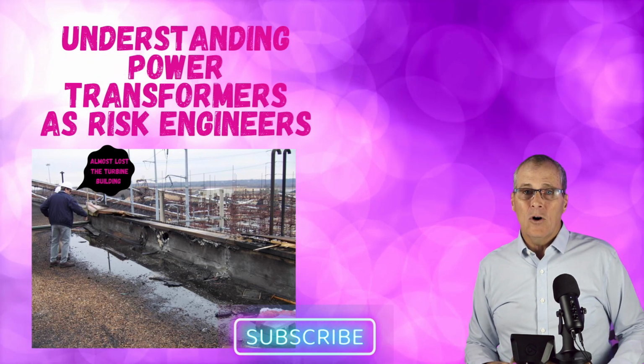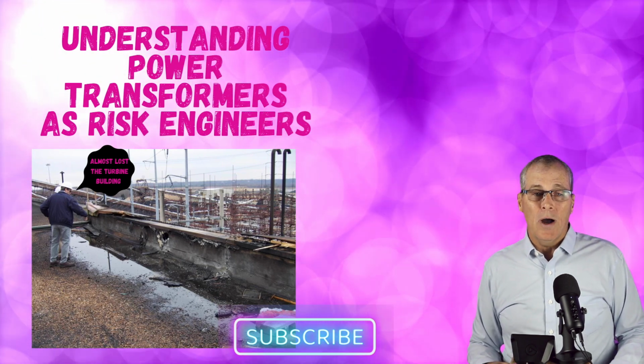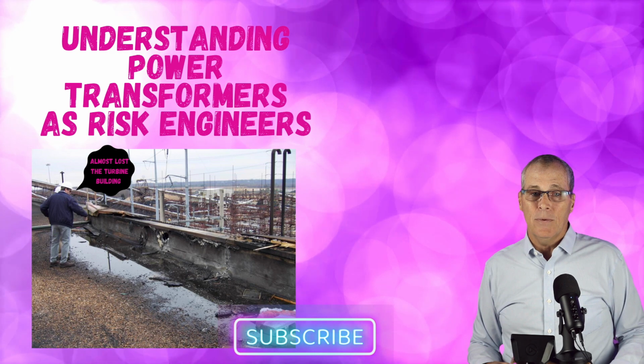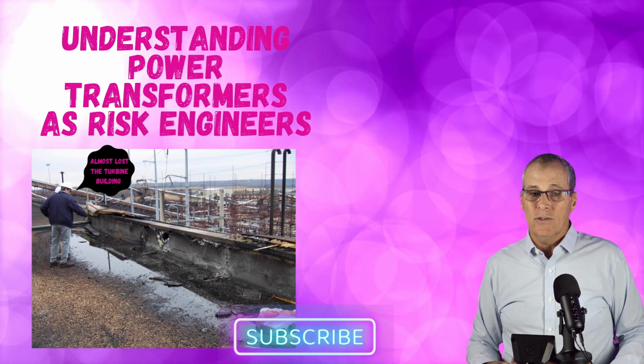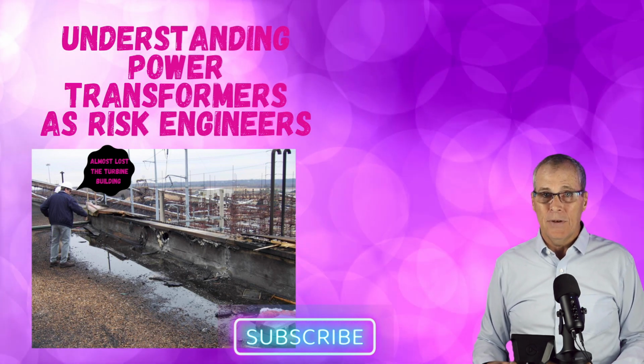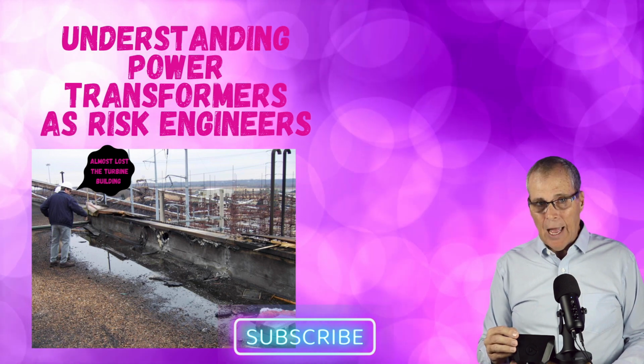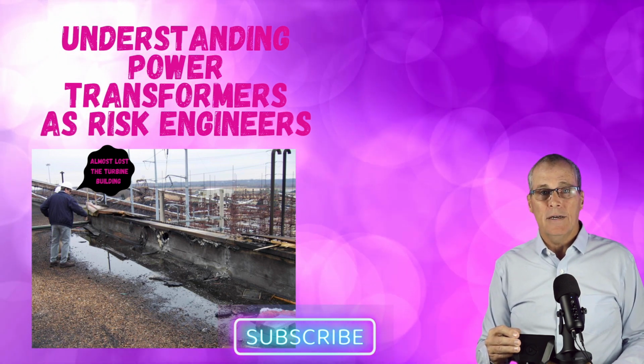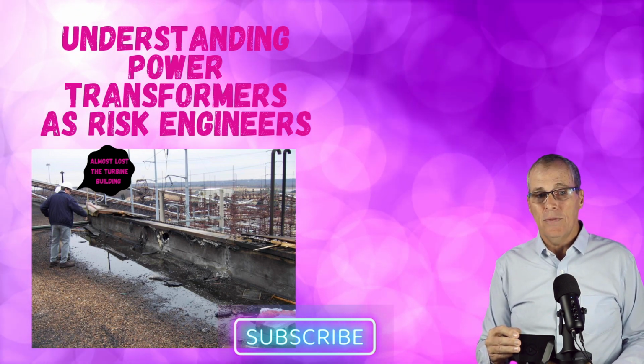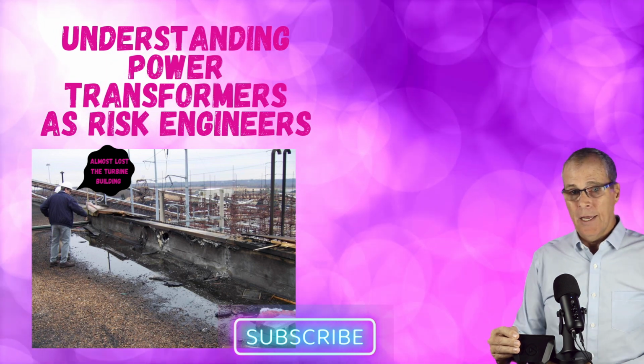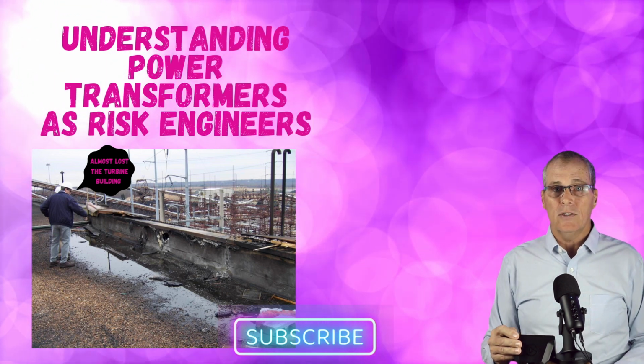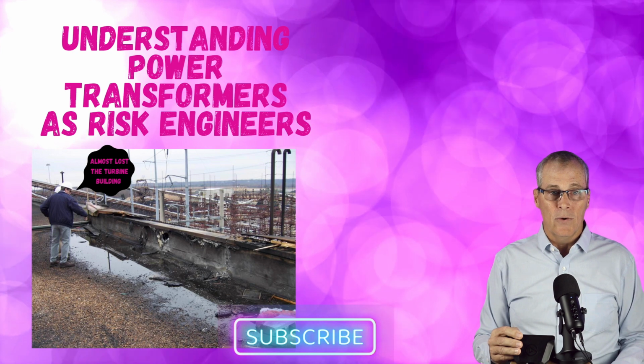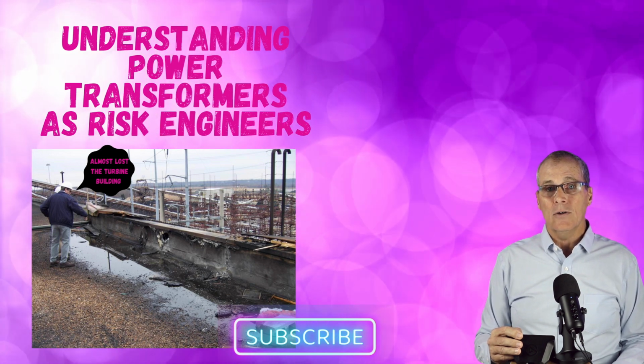Like I said, the fire was so hot, so big. This is the top of the turbine building, and you can see that it was going up into the roof. Had it got up into the roof, I think we would have lost the whole plant. There was really nothing to stop it. These firefighters weren't industrial, and there was nothing in the way of fixed systems that was going to stop a roof fire from rolling right across all the units.